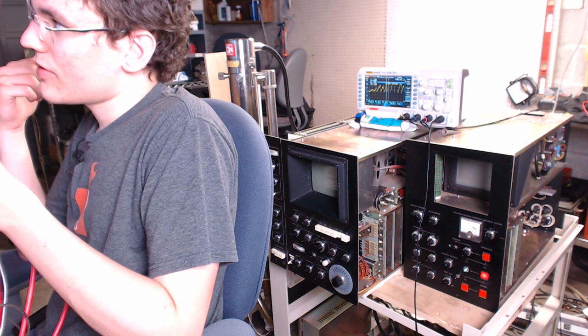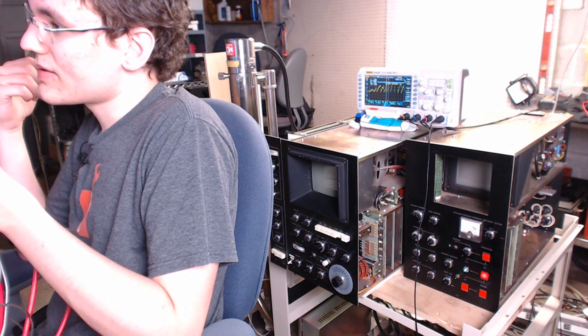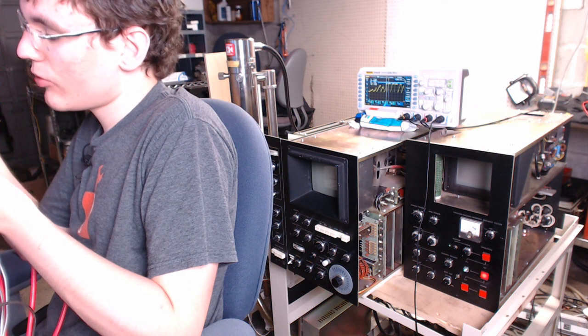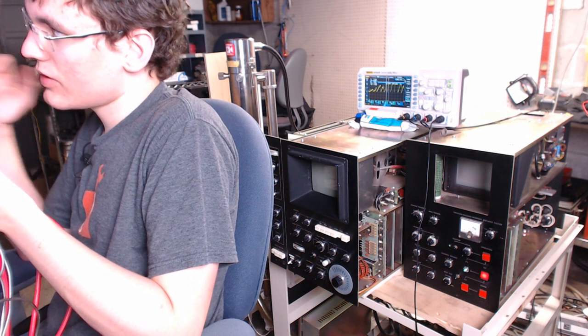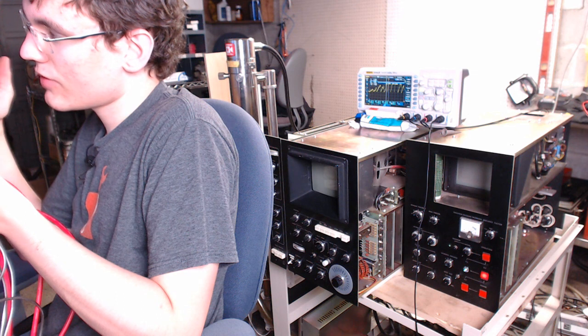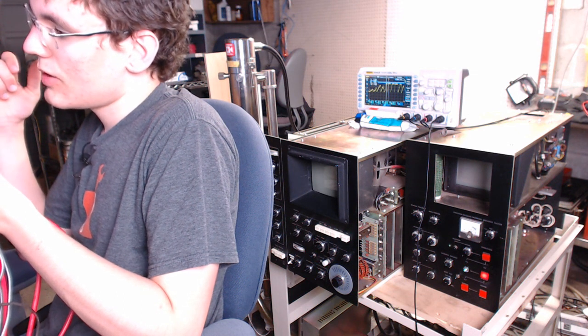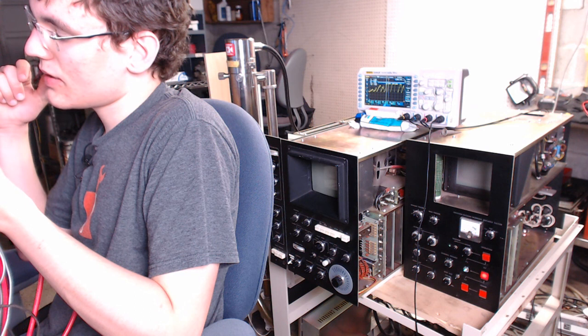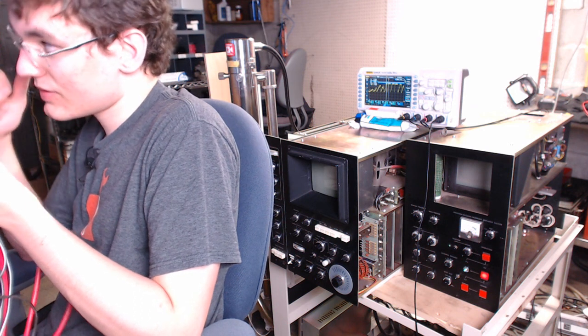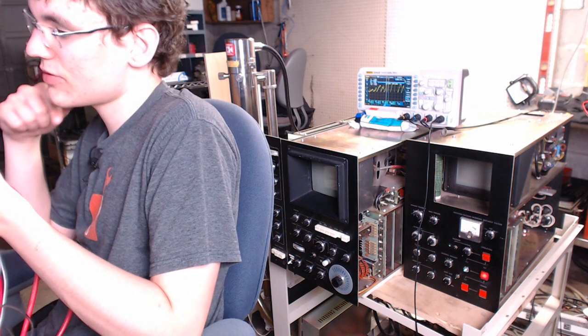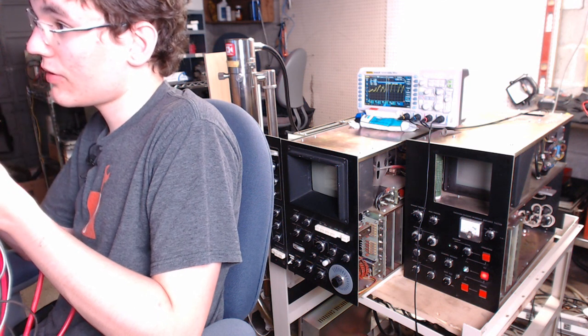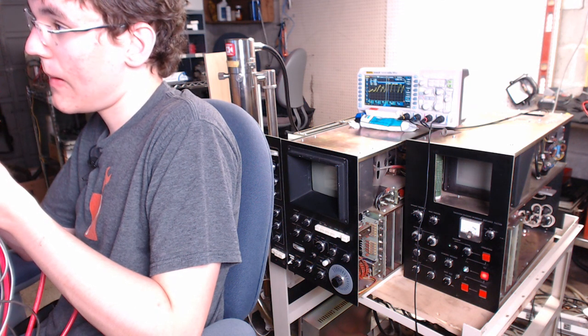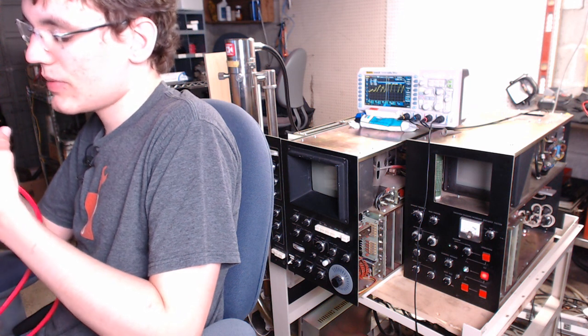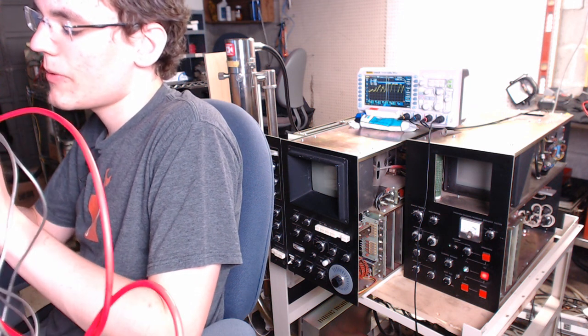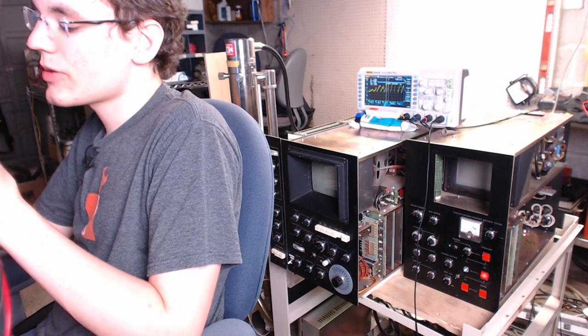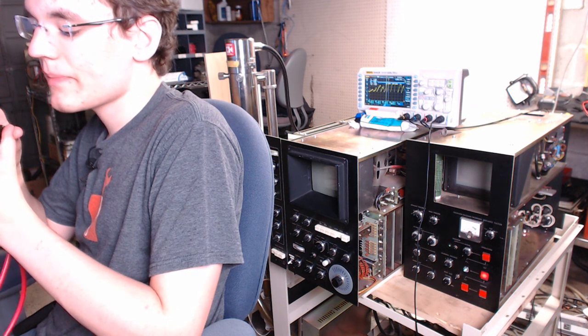Wow, the photomultiplier is already like 3 different steps to disassemble, and each one of those is pretty involved. So I gotta get the photomultiplier off, get the old scintillator mount off, get the old cage off of that one, get this thing mounted up, get the photomultiplier adapter mounted to this, then reverse the 3 steps to mount the photomultiplier, and then go from there. So yeah, that's at least a couple hours of work to do it carefully. So I really don't want to break any of my parts because I don't know if I can replace them.